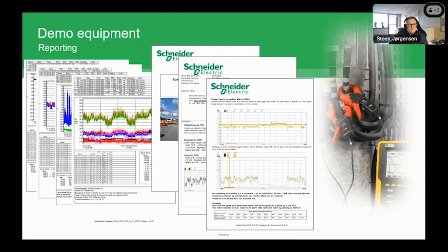Great, that is interesting. What do you need to consider when we do the installations of the fix of the power quality issue? Yeah, we have to be very aware of how the CTs are connected, because we need 3 CTs connected to the system. And if these CTs are located in a wrong place, we can actually pollute the system with more.